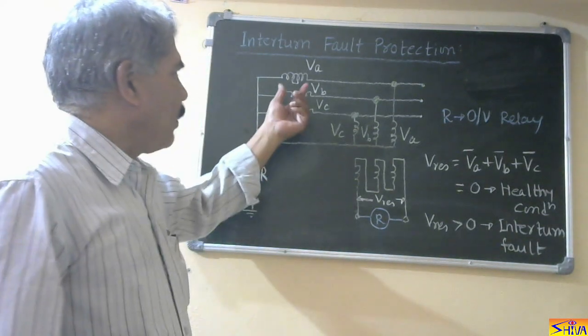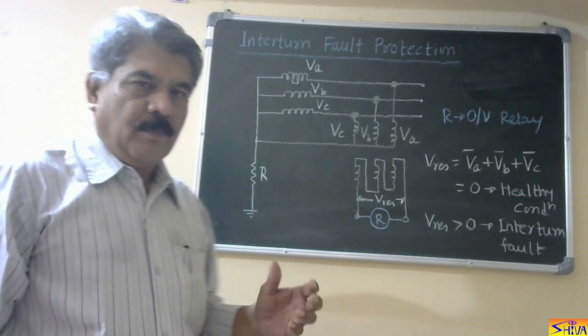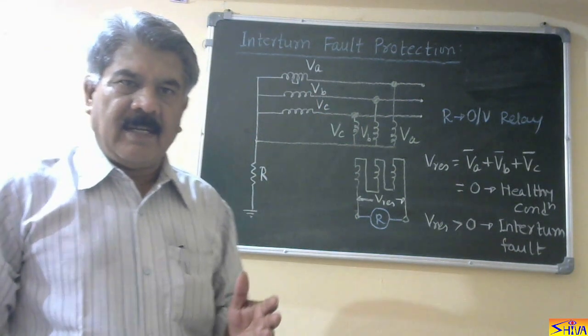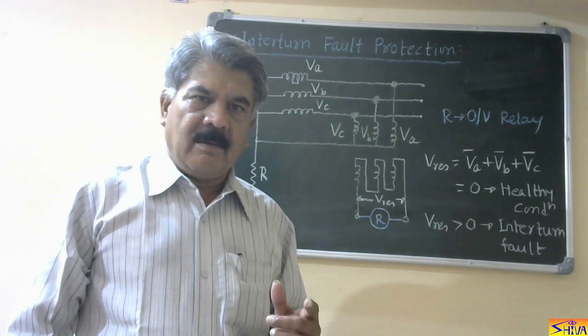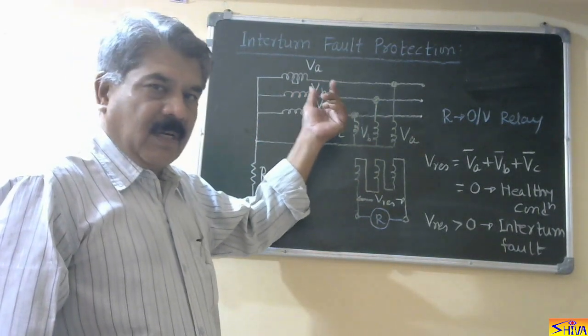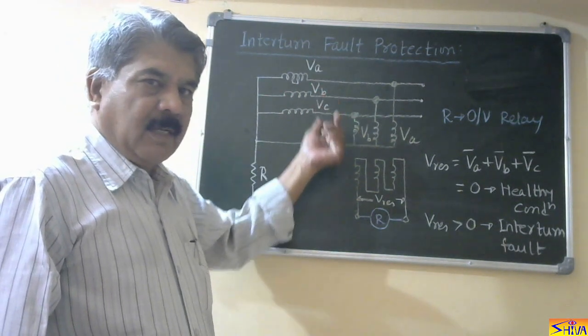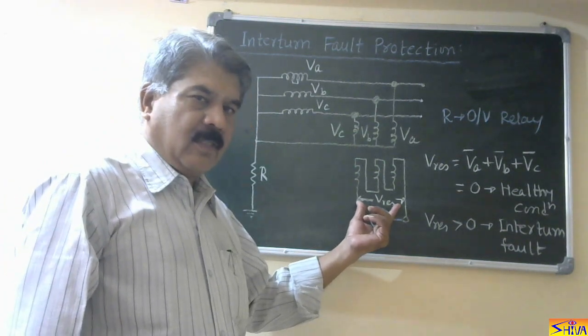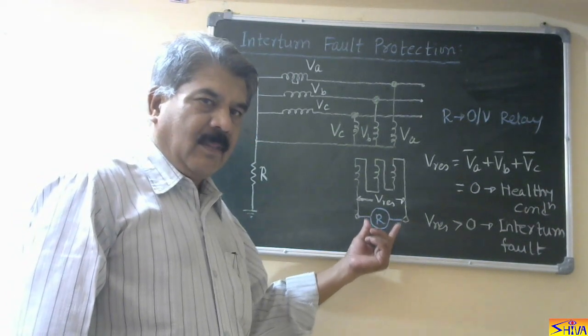Now, when an internal fault occurs — let us say in phase A — a few turns of the winding get short-circuited. So the induced EMF in that phase of the winding reduces, since the induced EMF equation is proportional to the number of turns. The induced EMF will reduce, so Va plus Vb plus Vc will no longer be zero, and we get some voltage across this open delta. If this voltage is higher than the pickup value of the over-voltage relay, then the relay trips.